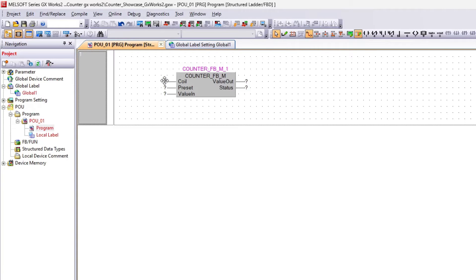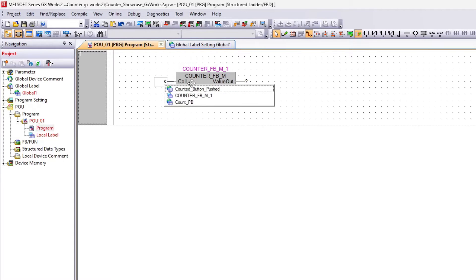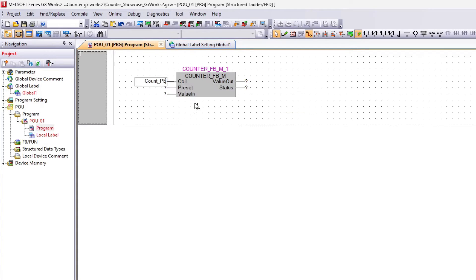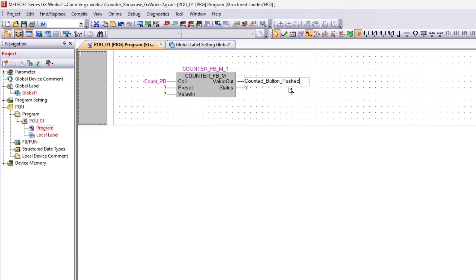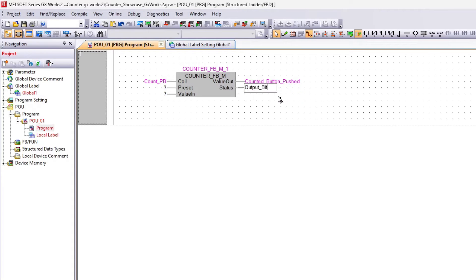Now we will add our tags to the block. The coil input is a bit tag that makes the Counter trigger. The valueout output is the tag that will show how many times the coil has been triggered, and it is a 16-bit word tag. The status output is a bit tag that will trigger once the value reaches the preset value.